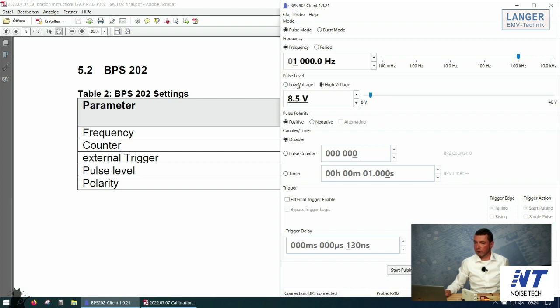Let's start with the low voltage range. With the slider or with these buttons here, you can change the value of the pulse. Pulse polarity, positive, negative, is something you also have to change during this testing. We started with the positive polarity. The counter timer is disabled because we don't need it for this calibration. The external trigger we also don't need here.